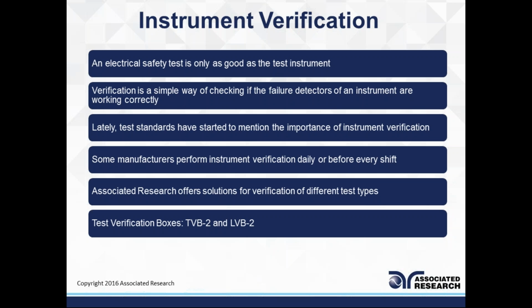Verification is a simple way of checking if the failure detectors of an instrument are working correctly. Again, this is not a very detailed process. It's as simple as taking a known load, for example a known resistor value, dropping a voltage across it and looking at the measured current. Then you can do the calculation by hand and compare that to the measured result, and see how accurately it is being measured and whether it's passing and failing when it should.